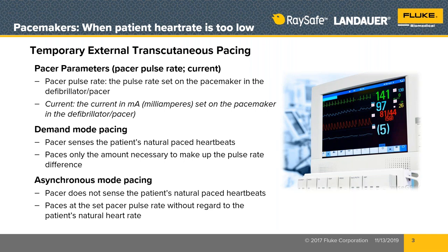Just to touch on that a little bit more, on demand pacing, if Jerry set that pacer at 60 beats a minute and your heart's beating at 65 beats a minute, there will be no pace pulses. We're not going to be discharging any energy to it. But in an asynchronous situation, if it's set at 60 beats a minute and your heart's still beating at 100 beats a minute, it's still going to be pulsing you 60 beats a minute. So you're going to be catching that shock every time. Right. And for that reason, there's not a lot of asynchronous pacing that really goes on much anymore. Mostly we're doing demand pacing.